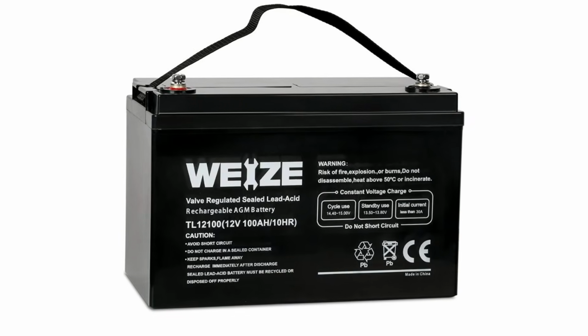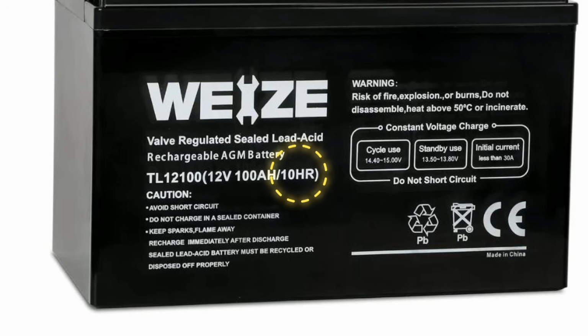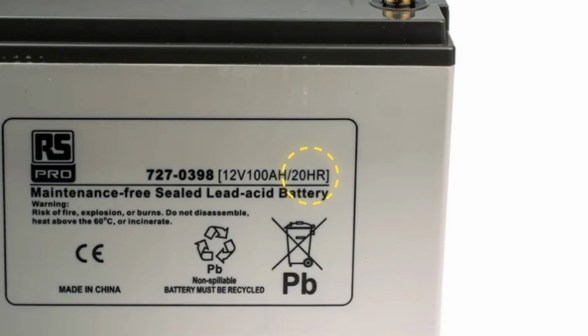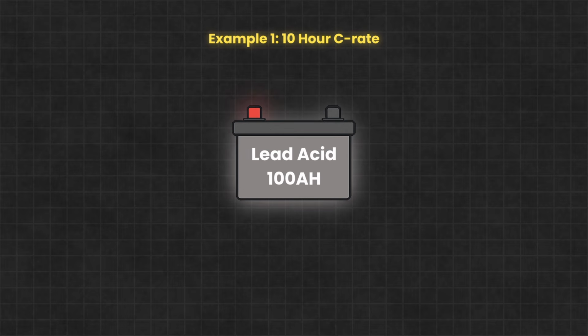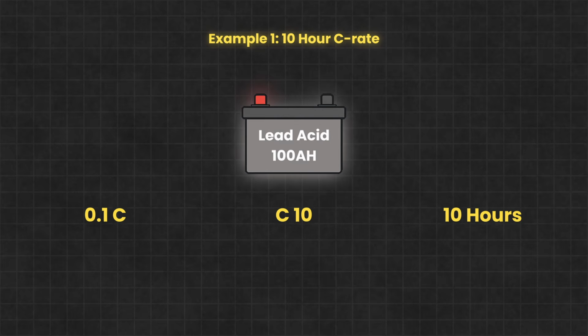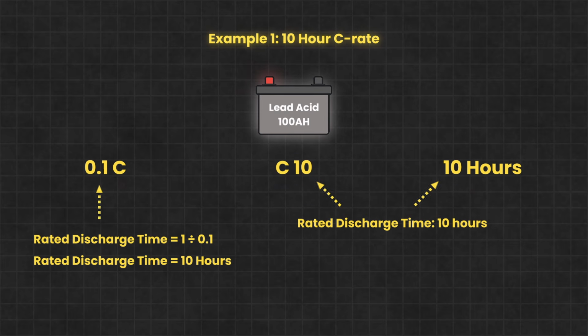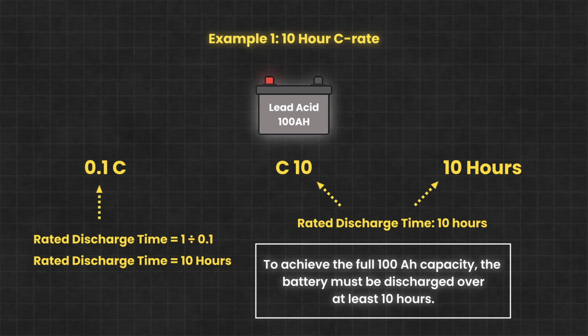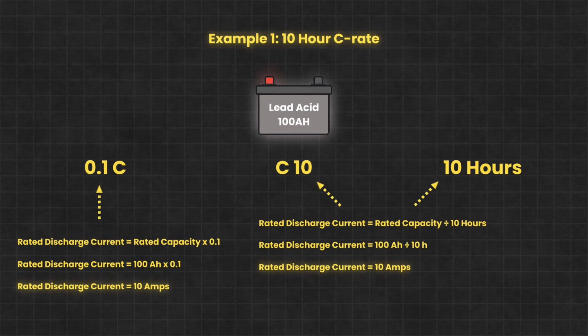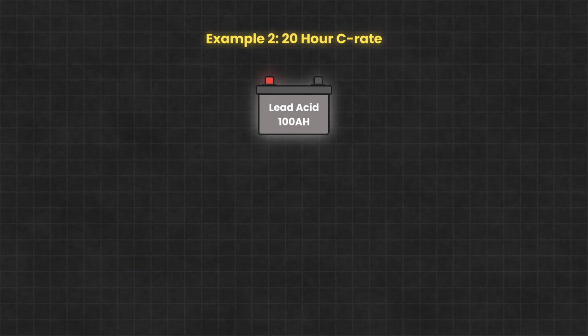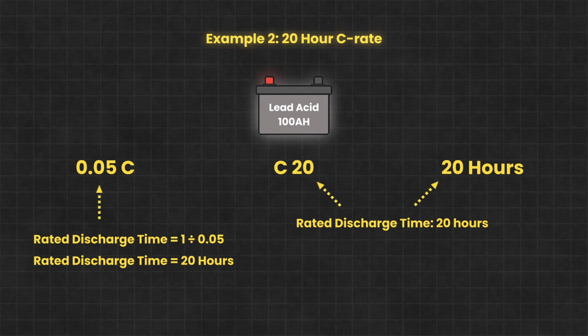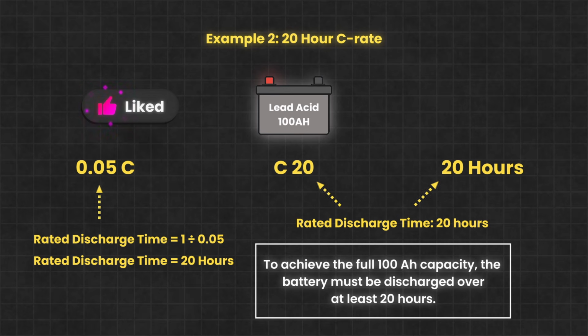Consider a lead-acid battery that's rated at 100 amp hours, for example. Most lead-acid batteries are rated at either a 10-hour or 20-hour C rate. So when you see ratings like 0.1 C, C10, or just 10 hours, they all mean the same thing. If one of those ratings was printed on the battery, it would mean this. To get the full 100 amp hours out of it, the battery would need to be discharged over a period of no less than 10 hours. In other words, the advertised 100 amp hours capacity is only accurate if the battery is discharged at 10 amps or less. Now let's say the manufacturer gives a rating like 0.05 C, C20 or 20 hours. That means to get the full 100 amp hours, the battery should be discharged over 20 hours or at no more than 5 amps.